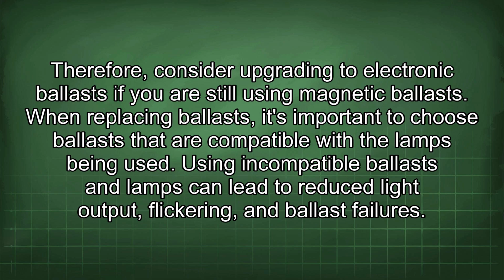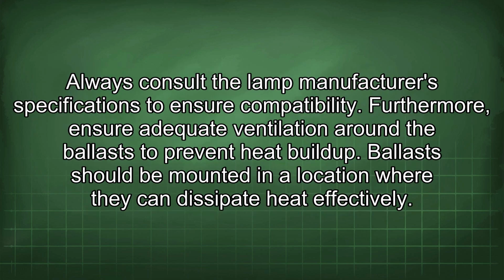When replacing ballasts, it's important to choose ballasts that are compatible with the lamps being used. Using incompatible ballasts and lamps can lead to reduced light output, flickering, and ballast failures. Always consult the lamp manufacturer's specifications to ensure compatibility.